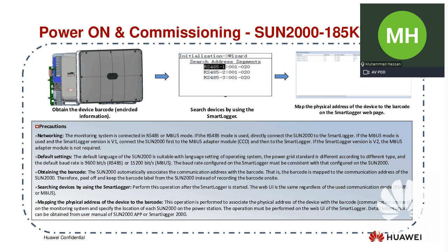But for the utility scale, always obtain the barcodes for that inverter, so that you can upload that barcode. You can upload the serial numbers of that inverter as per your inverter name, and also the COM addresses into that smart logger. As I mentioned before, the smart logger is the device which is used to communicate with multiple inverters. The Smart Logger 3000 can communicate with up to 180 devices, so you can control 180 devices with a few clicks or a single click.